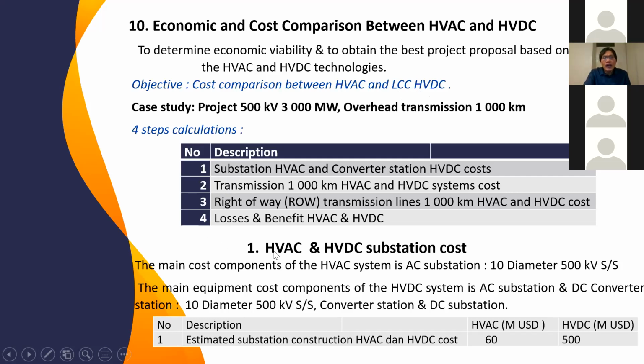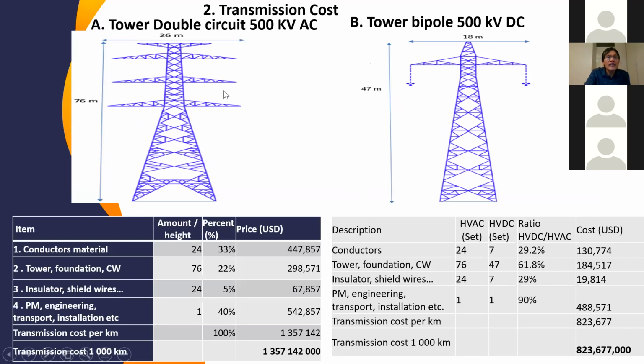For substation cost, with 500 kV, the assumption is we have a 10 diameter 500 kV substation, costing 60 million, while for the converter station, we consider 500 million US dollars. And for the transmission line, we need a double circuit for AC with a 26 meter arm and a total tower height of 76 meters, while for DC only an 18 meter arm and 47 meter tower height. So in order to compare, we have 4 parameters here: conductor material, tower foundation civil works, insulator and ground wire, project management, engineering, transport and installation, with certain weighting factors.